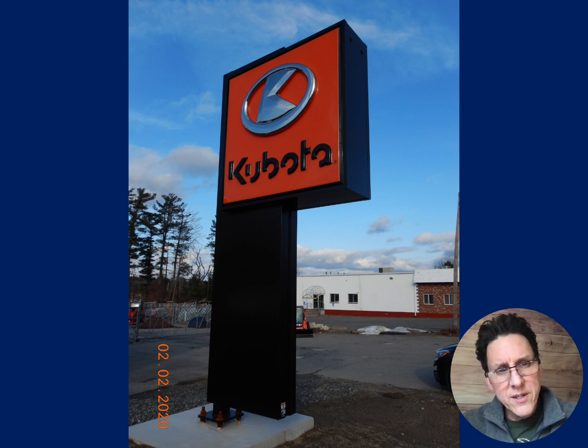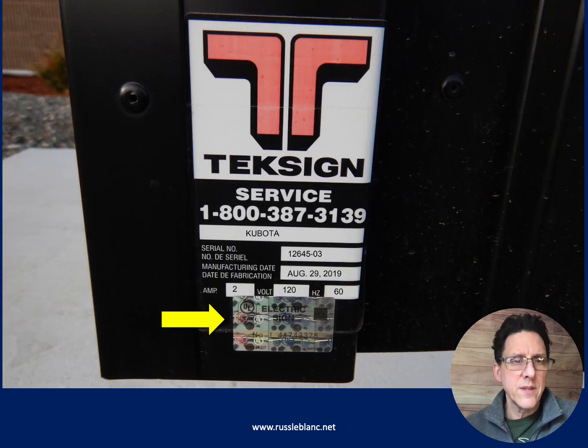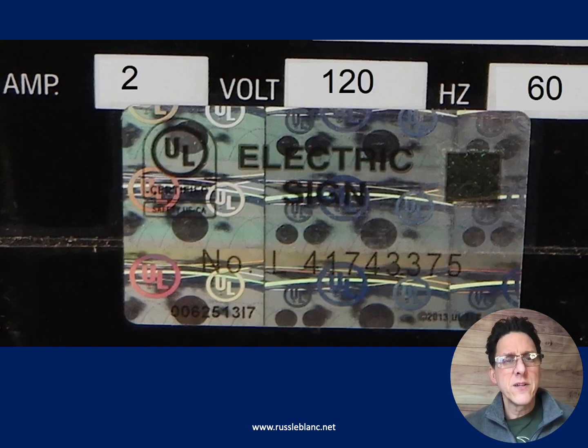If you look close, on the very bottom of the sign, you can see where the label is and the UL mark. I'm going to zoom in on that. There you go. Right, so we have the amperage and the voltage there, and we also have the label from UL there. If we zoom in on that, you can see that that piece of equipment is listed as an electric sign.